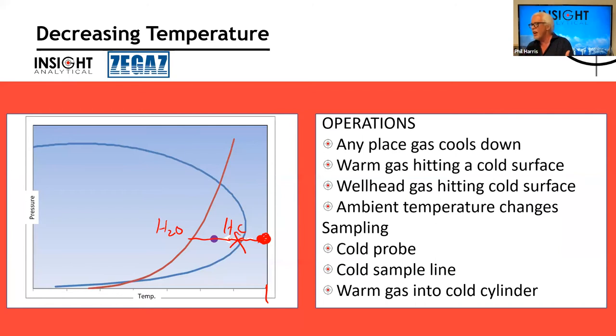If we have warm gas hitting a cool surface, if your gas is warm, we're in a place like Saudi or Qatar, and the natural gas is warm, and we bring it inside of an analyzer building that's air conditioned, as soon as that gas hits a cold piece of tubing, we can start to condense out liquids. Wellhead gas coming up from the well is warm, hits the cold tree at the top of the well, boom, done. Condensation right there. And of course, like I said, Canada, just ambient temperatures.